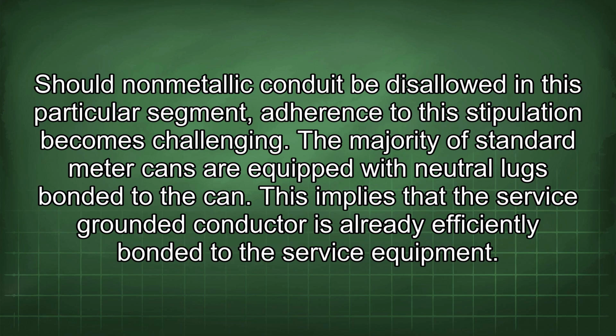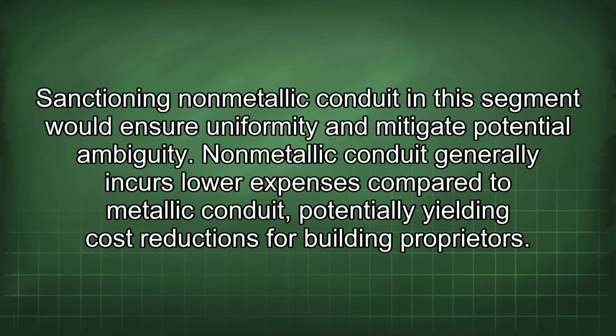The majority of standard meter cans are equipped with neutral lugs bonded to the can. This implies that the service grounded conductor is already efficiently bonded to the service equipment. Sanctioning nonmetallic conduit in this segment would ensure uniformity and mitigate potential ambiguity. Nonmetallic conduit generally incurs lower expenses compared to metallic conduit, potentially yielding cost reductions for building proprietors.